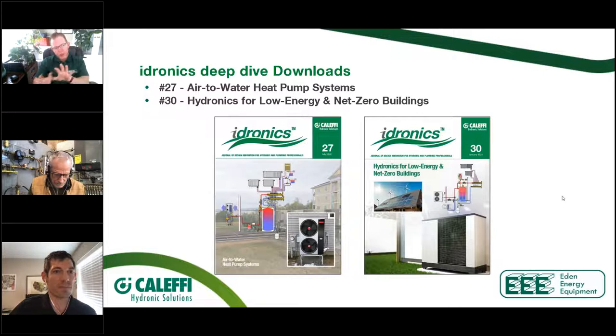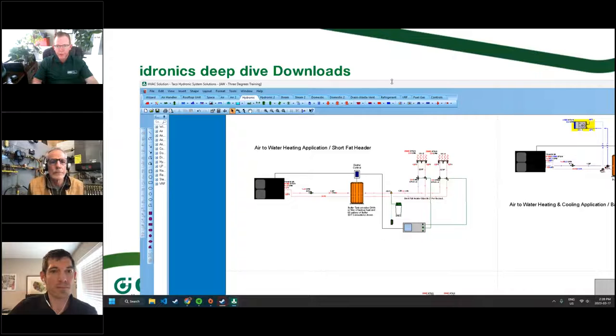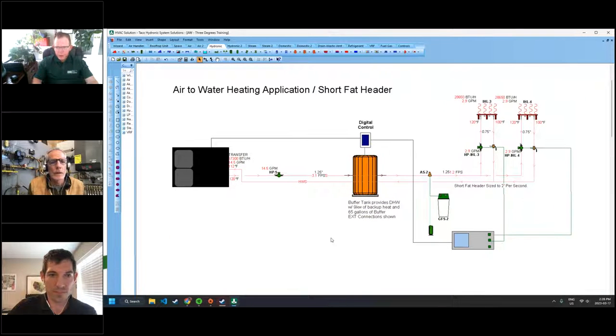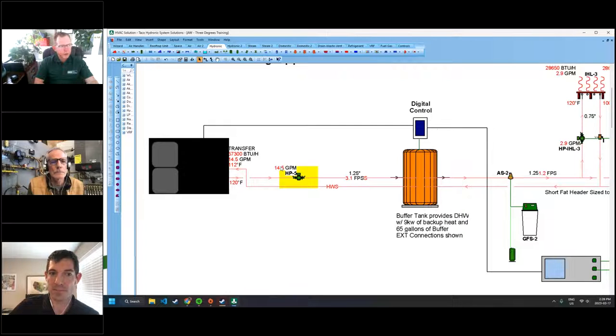And at this point, we're actually just going to segue away from this, and we're going to switch screens here, and we're going to start talking about some of the systems and get some feedback from Bob and Max as we go. So these are not drawings that we did in particular for this. These are just drawings we use in general. I've probably got a few thousand drawings on my computer that we tweak and adjust for customers as needed. So in this case, this is actually the drawing I did conceptually for my house. And so what you'll notice is the 57,300 BTUs over here, and you'll see that it's 14 and a half gallons a minute. So again, this is where a lot of people go, why is that coming into play? But look at the lift on the equipment. This equipment isn't lifting the water 20 degrees and we don't care. And so this pump has to be sized accordingly. And the other thing that comes into play is that this piping has to be sized accordingly. We need to make sure that we try to keep that piping in a 2 to 4 feet per second range.